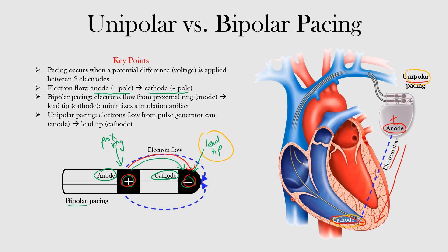Furthermore, currents flowing from the pulse generator can into the lead tip may stimulate excitable tissue between the two, and this can result in large stimulation artifacts that we see on the EKG. In bipolar pacing, the anode and cathode are located within the heart, which helps to minimize this stimulation artifact.